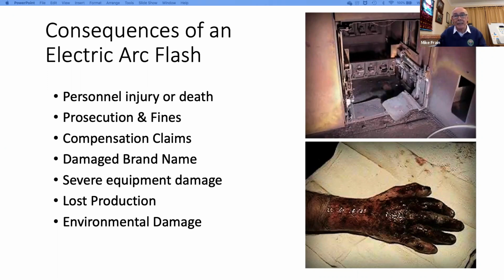That is a non-biodegradable poison. It gets into the atmosphere or into rivers or the waters, and you can't get rid of it basically. But it's nasty when it burns as well, and I had to alert the fire brigade commander to get his officers tested for dioxins, and they were all shipped off to the local hospital because of what was given off by the fire. And then I had to arrange for a company to deal with the liquid remains of the oil and the PCBs that were about to be discharged into the nearby river. It was actually the river down at Rotherham. And we averted that by being able to skim all that poison and oil off the top of the bund.